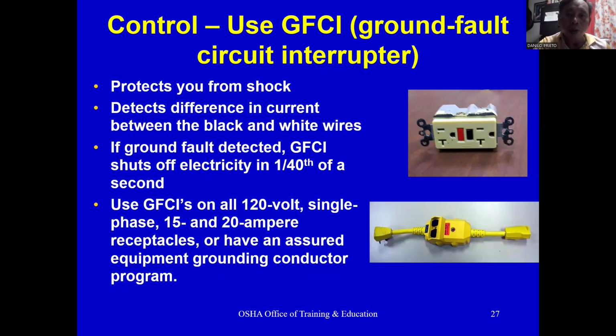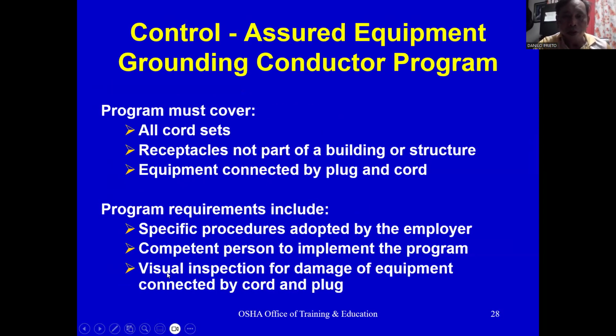Next, control: use GFCI, the ground fault circuit interrupter. It protects you from shock and detects the difference in current between the black and white wires. If a ground fault is detected, the GFCI shuts off electricity in 1/40th of a second. Use GFCIs on all 120 volt single phase 15 and 20 ampere receptacles, or have an assured equipment grounding conductor program.